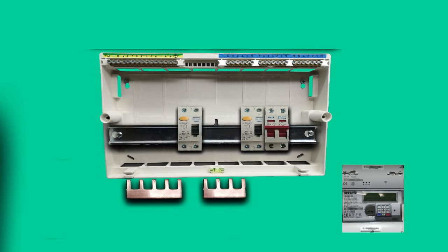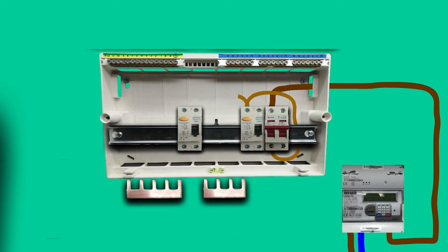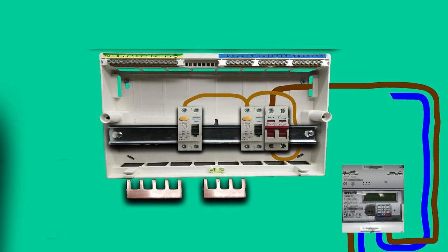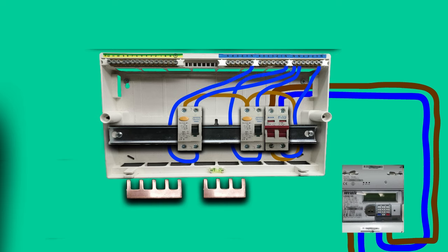So now let's have a look at how all the wiring of the consumer unit looks. The line meter tail goes from the meter to the line terminal on top of the main switch and from the bottom of the switch it supplies the first RCD and the second RCD. Then the neutral tail from the meter goes to the neutral terminal of the main switch and from the switch to the first section of the neutral bar. From the same neutral bar two neutral conductors go into the neutral terminal of both RCDs, and then from each of the RCDs the conductors go to the corresponding sections of the neutral bar.